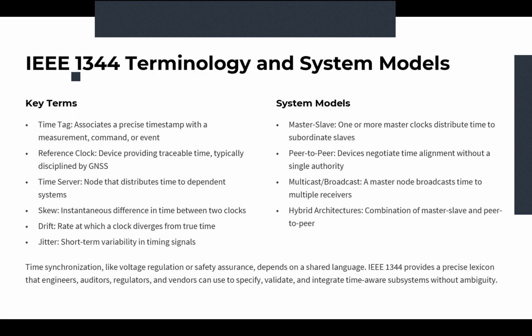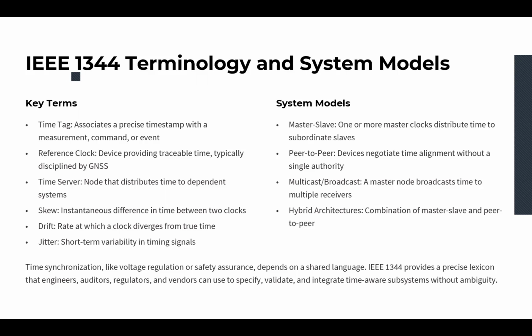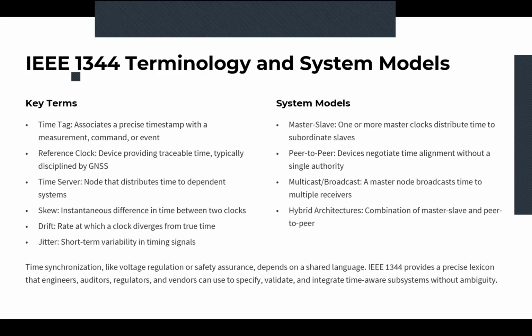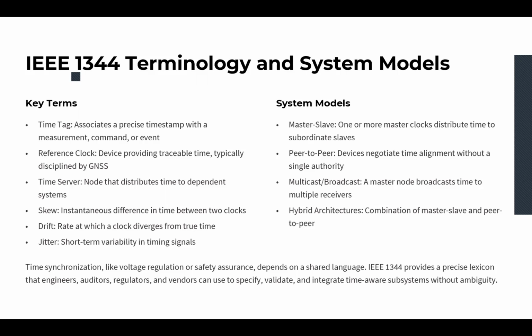We have reference clock as a terminology, which is the root authority for the time. It typically is a GPS, a rubidium source, or a cesium atomic clock. It's the main reference that tells us the exact precise time, and we have to synchronize everything with that clock. So it's the center of our synchronization. We have time server as a term, which is a node that distributes its time to the downstream clients. It could work with the NTP protocol or PTP. We don't enforce any protocols. So the time server distributes the time from the main reference to all the clients, all the downstream hierarchy that we talk about.